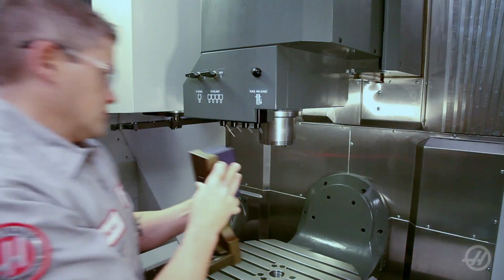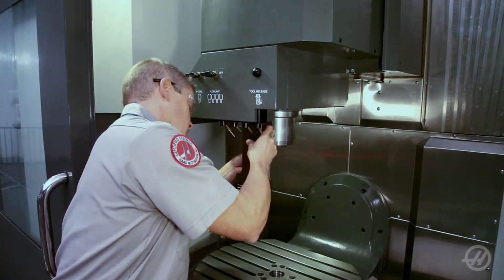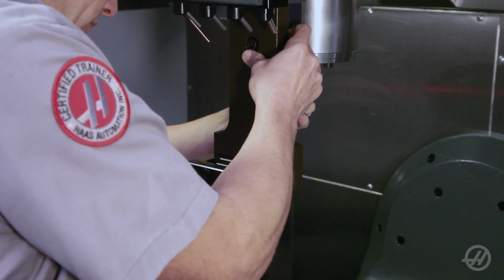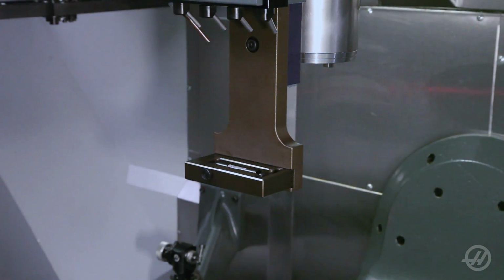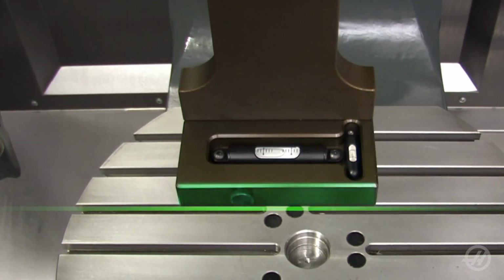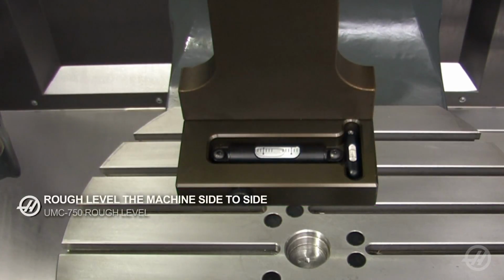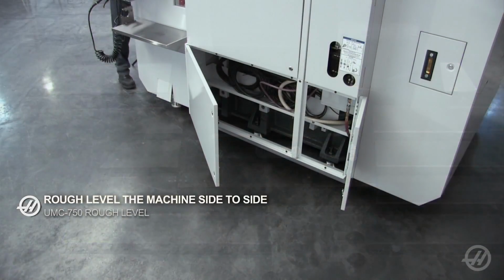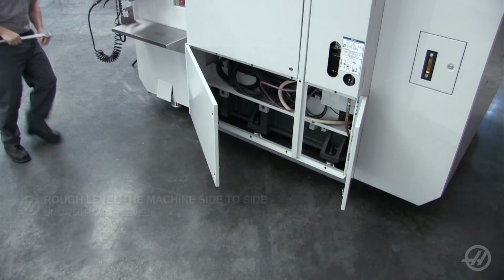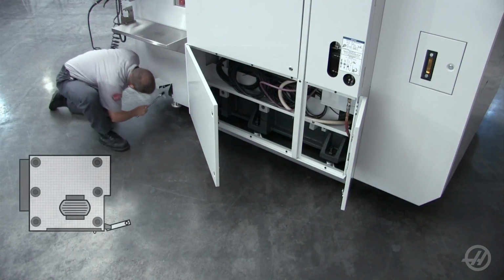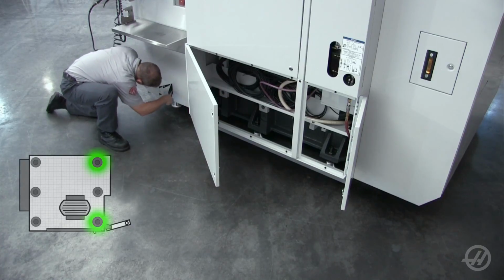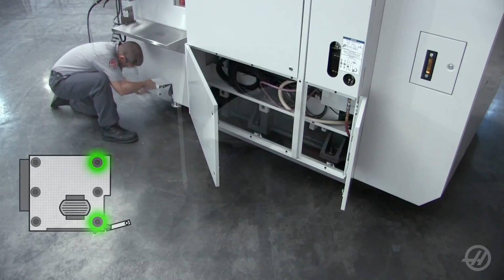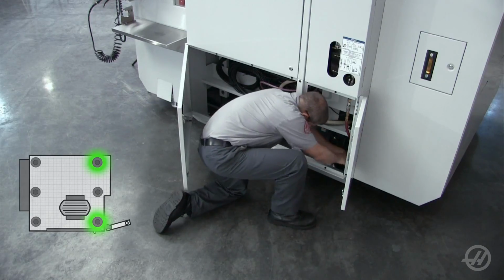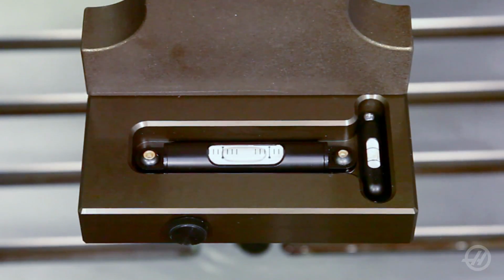Attach leveling tool T2192 to the spindle housing with a precision level parallel to the X-axis. Visually verify that the edge of the level lines up with the T-slots. First, we'll level the machine side to side. Choose the side of the machine you want to adjust and lift or lower that side with even adjustments of the 2 screws on that side until the bubble is centered.